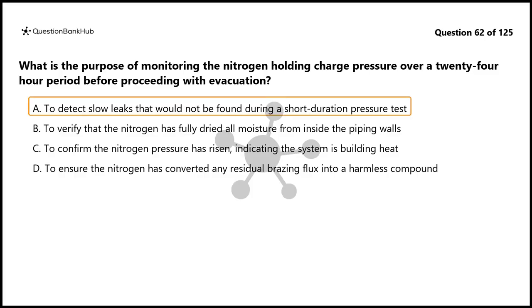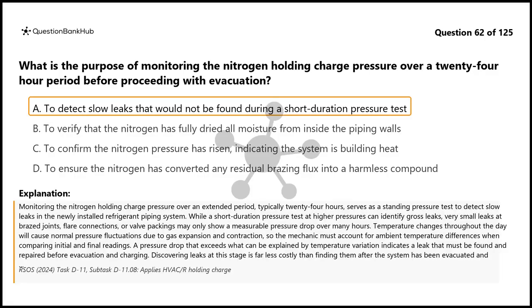The correct answer is A. Monitoring the nitrogen holding charge pressure over an extended period, typically 24 hours, serves as a standing pressure test to detect slow leaks in the newly installed refrigerant piping system. While a short-duration pressure test at higher pressures can identify gross leaks, very small leaks at brazed joints, flare connections, or valve packings may only show a measurable pressure drop over many hours.